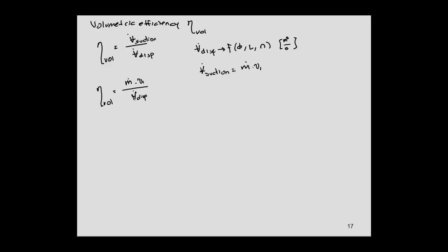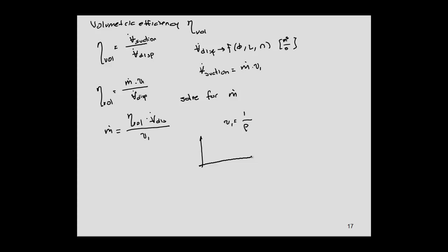Substituting, the volumetric efficiency equals mass flow rate times specific volume at the compressor inlet divided by the displacement rate. Solving for mass flow rate: mass flow rate equals volumetric efficiency times the displacement volumetric flow rate divided by the specific volume at the inlet — noting that specific volume is the inverse of density. Because of this, if we compute capacity versus evaporation temperature, we get a characteristic curve, which we'll work through in an example.